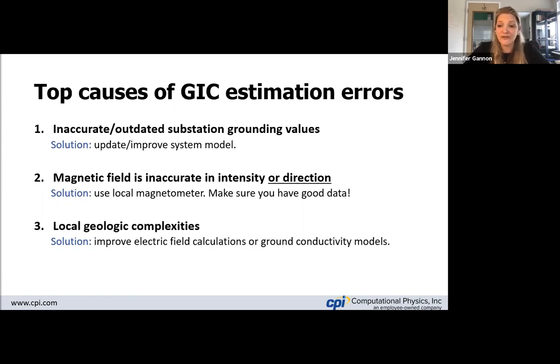If you're trying to use magnetic field data to do a model validation, number one, your substation grounding values have a huge impact on your result. Maybe you've measured the substation resistance 40 years ago, and it's rained a lot since then, and there's corrosion on your grounding mat that's changed the value, which can change the parameters in your system model. Maybe the storm you measured had a significant line out of service at the time. You need to make sure the system model matches the conditions during which you measured your magnetic field. That can clear up a lot of first order issues.